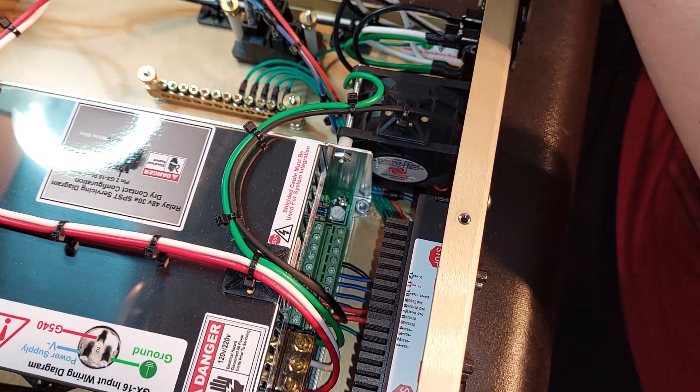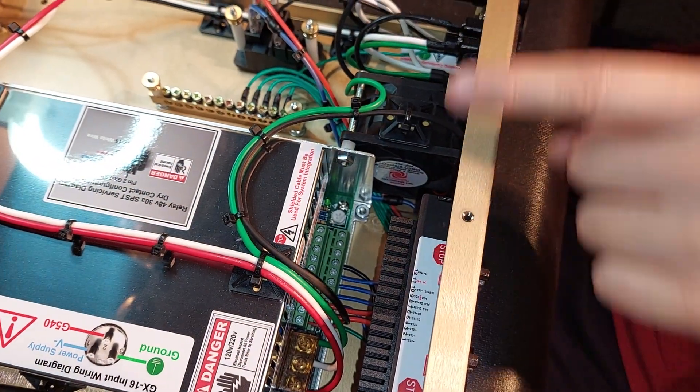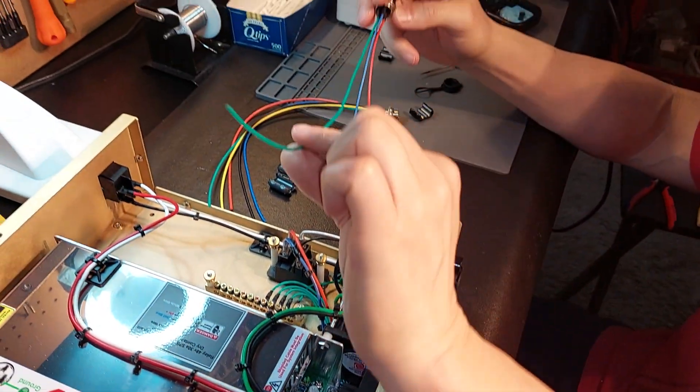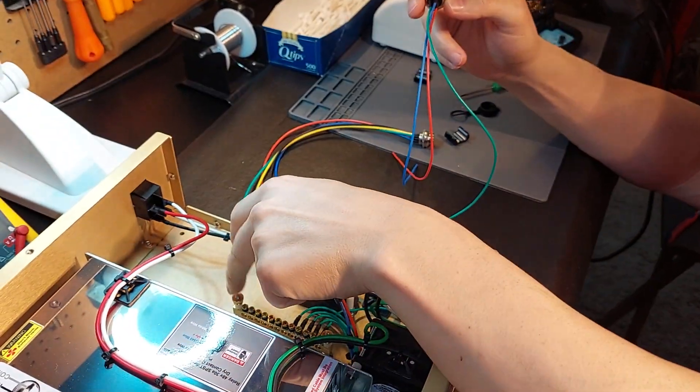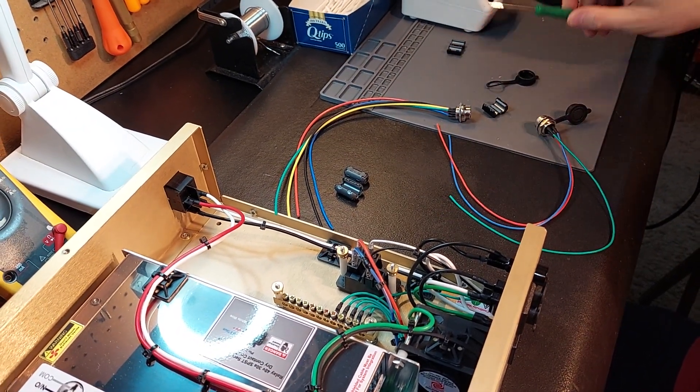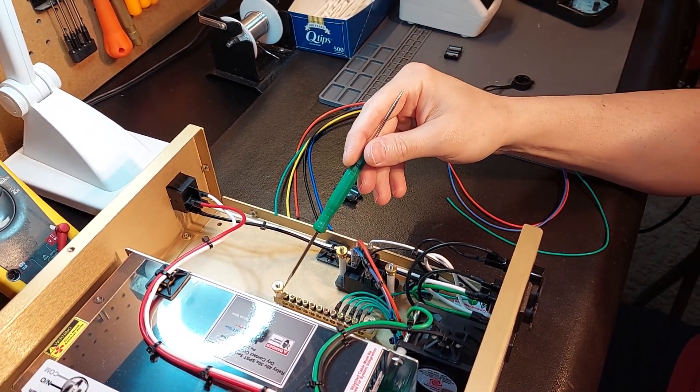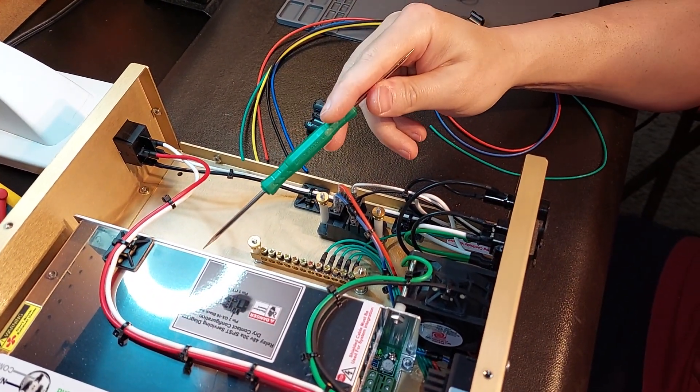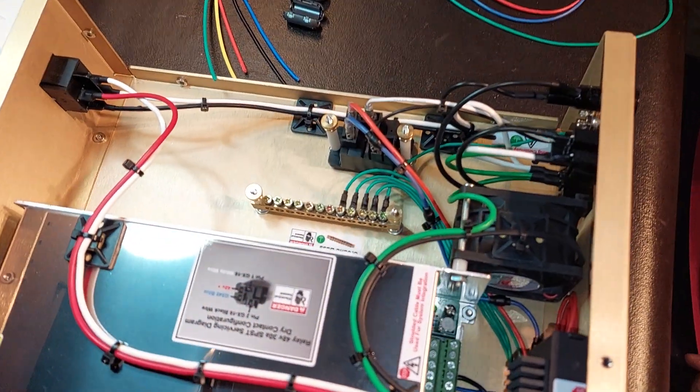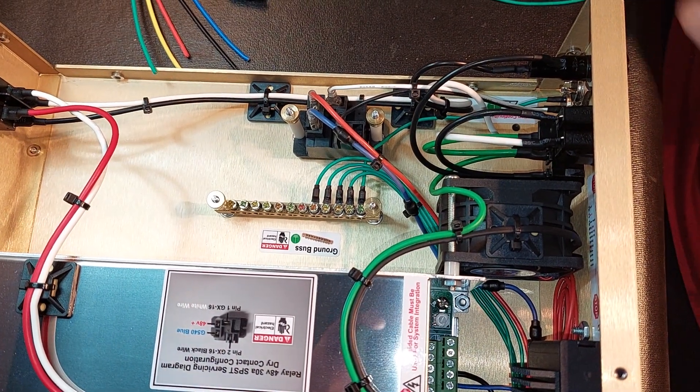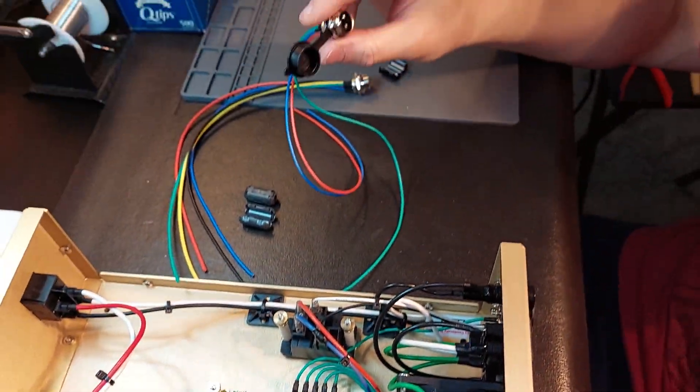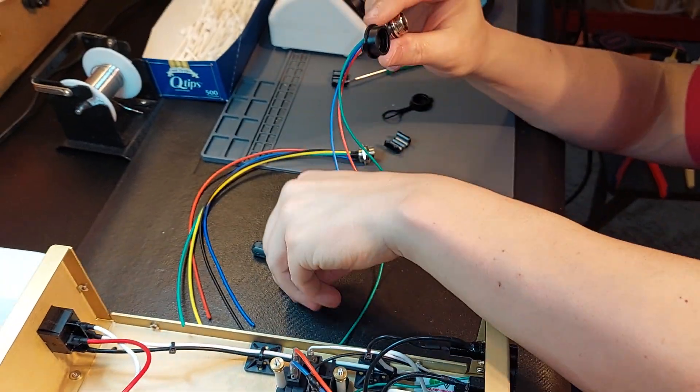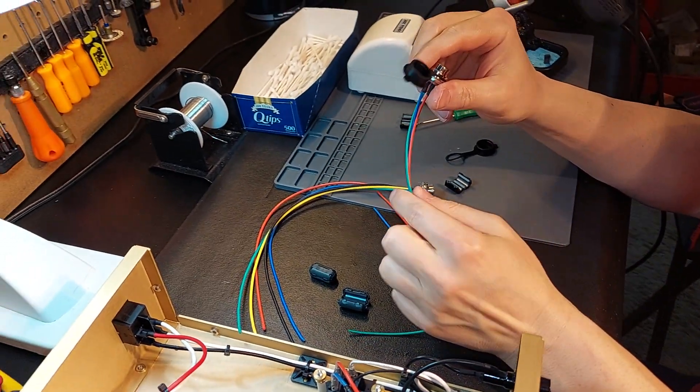Why I like using this it's a great demonstration to see exactly how things are done. Our green lead which is our ground is for our shield drains going to our bus bar. We always check our system for continuity to make sure we have full continuity conduction on the ground of the power supply to the actual bus bar. You can see just how much time these will save you. You don't have to guess about ferrites, these units come with ferrites as well.